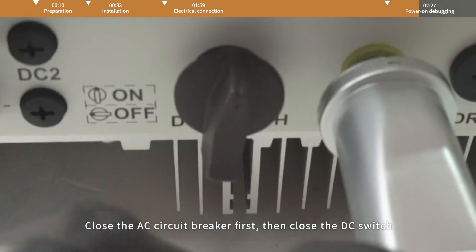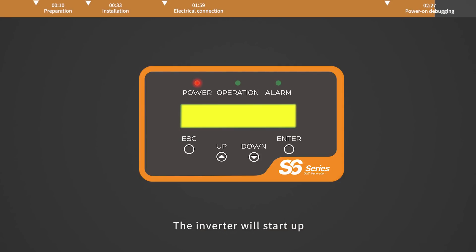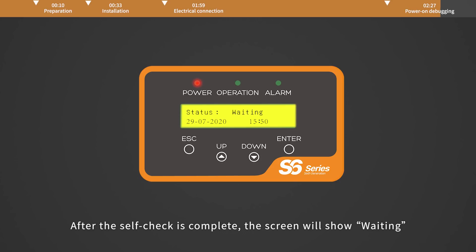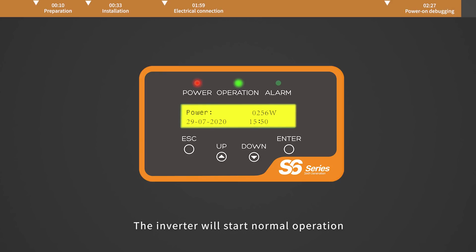Then close the DC switch. If the DC input voltage is greater than the startup voltage of the inverter, the inverter will start up. After the self-check is complete, the screen will show waiting. After the local mandatory delay ends, the inverter will start normal operation.